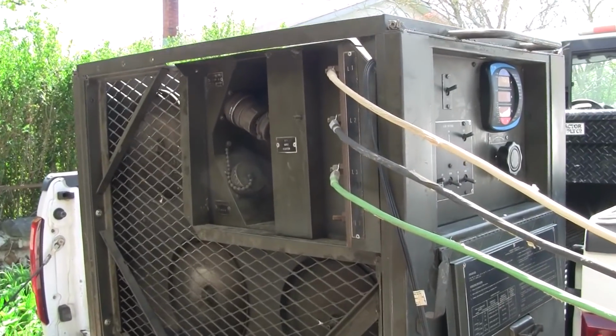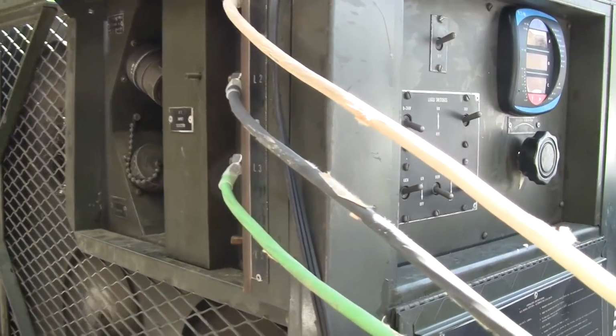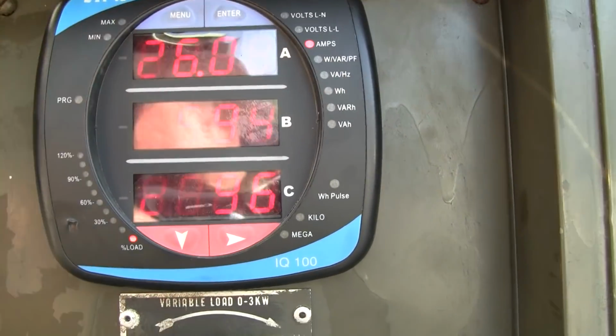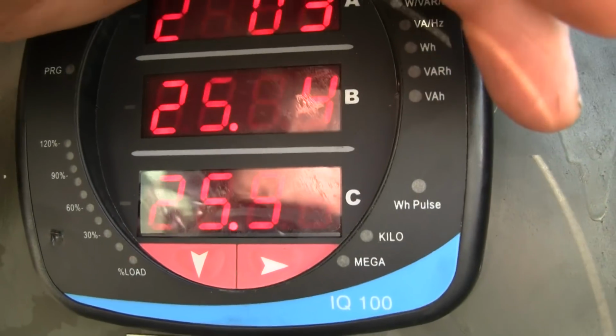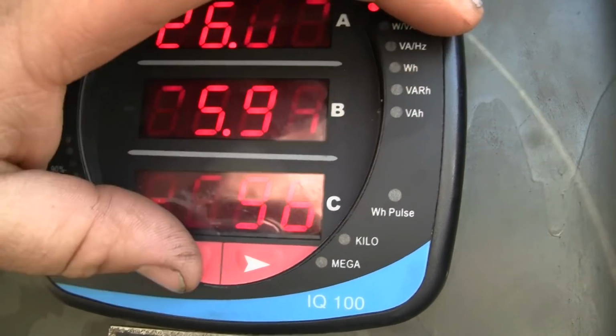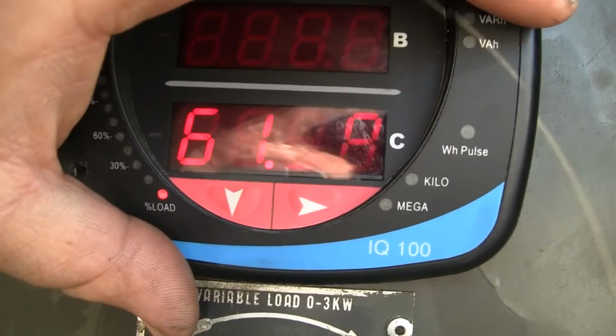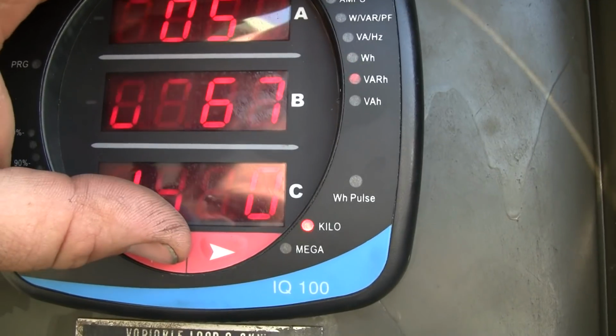Well, we've been running at 50% load for a little while now. Got some heat in the engine. Let's see. We're still at 25, 26 amps. Boy, this meter here really messing with the camera. 25, 26 amps, frequency still good. 61.3, 61.4. Let's take it up to 50 amps.